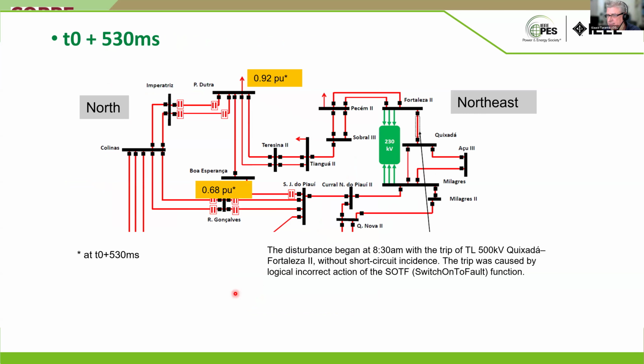This is a localized one-line diagram of the 500 kV lines. All in red are 500 kV lines. There is one transmission system here, 230 kV, but it's not that important. And this line here is where the disturbance began, at 8:30 a.m. This line tripped without any short circuit. The trip was caused by the logical incorrect action of the SOTF, switch on to fault function.